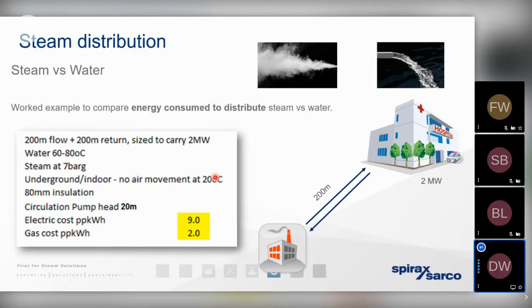But we know that with a liquid-based system, if we're comparing steam to water, we do need to pump that water. And the thing to bear in mind is whenever engineers are benchmarking the benefits of water against steam, quite often they quite rightly identify that because we're generating steam at higher pressures and therefore at higher temperatures, we need to consume more gas. Of course we do. We recognize that. But the thing to bear in mind is the cost of pumping that liquid energy, that low temperature hot water. The pumping costs can quite often outweigh the benefits in generating that low temperature hot water with a lower gas consumption.